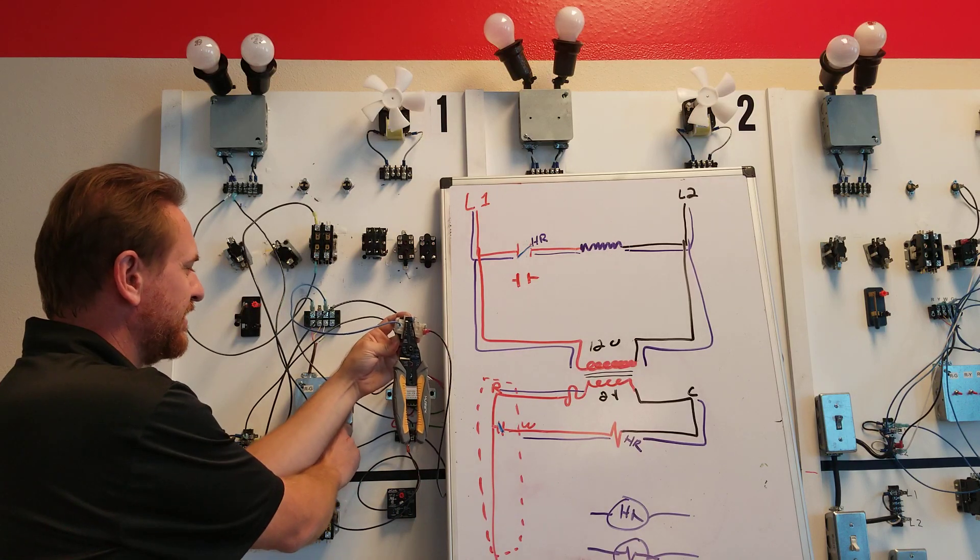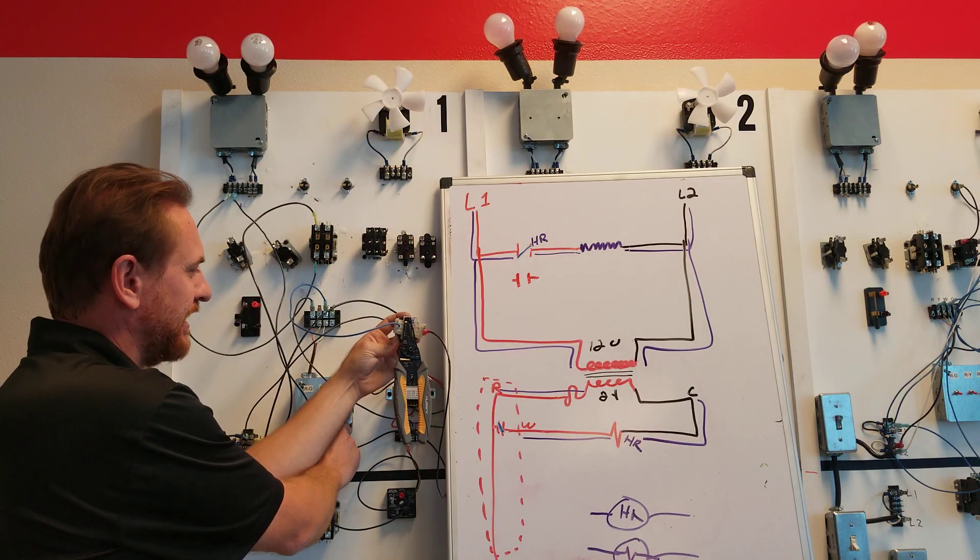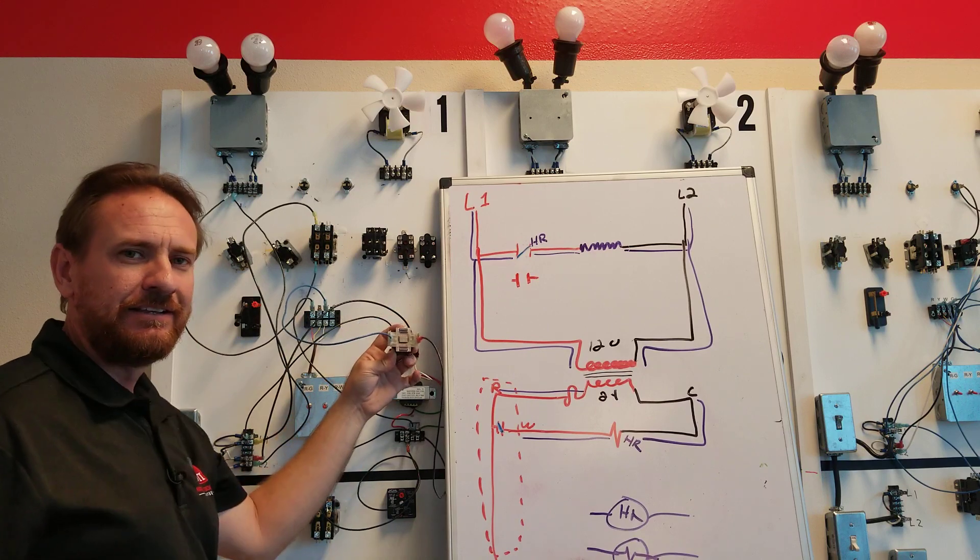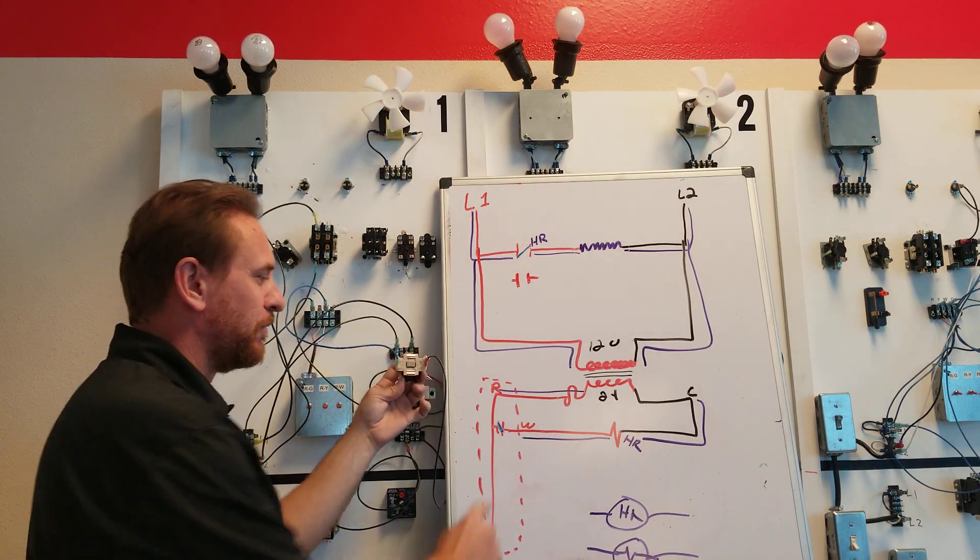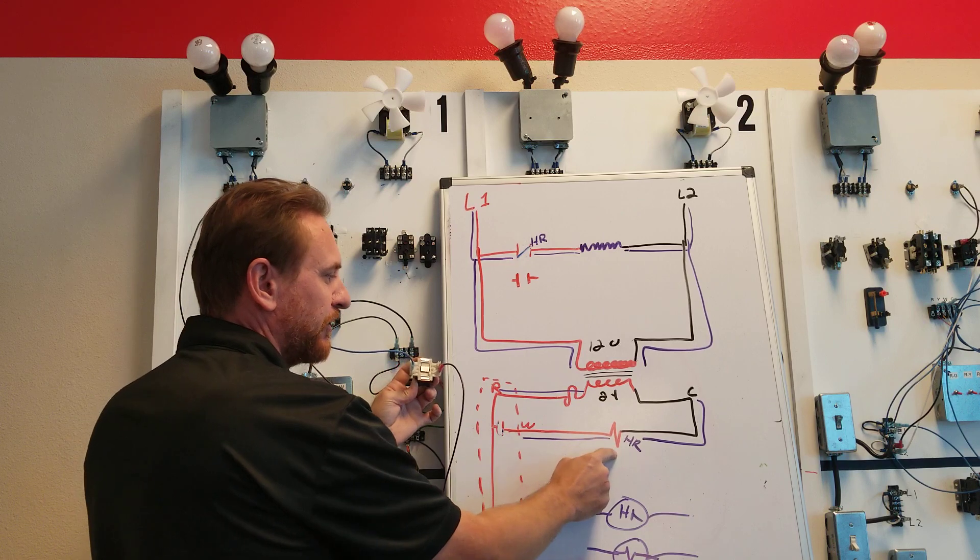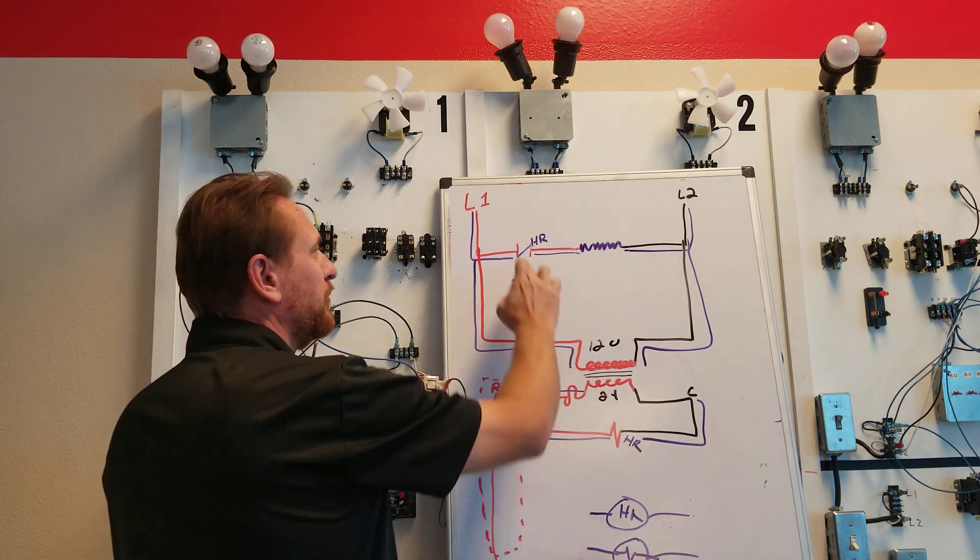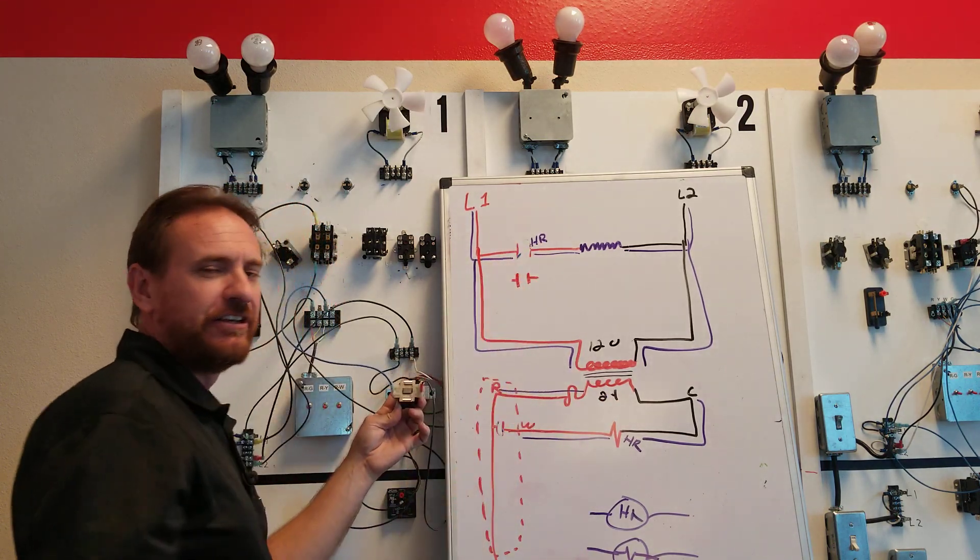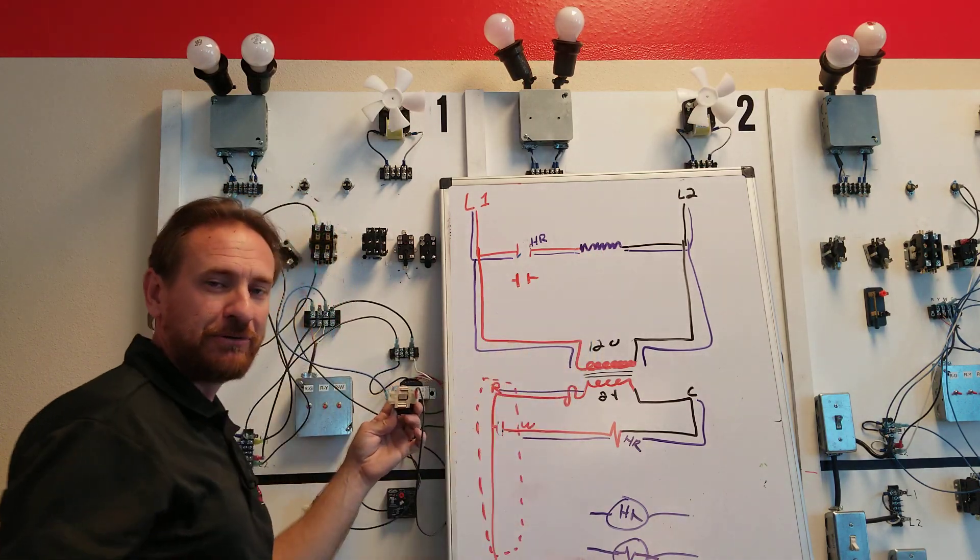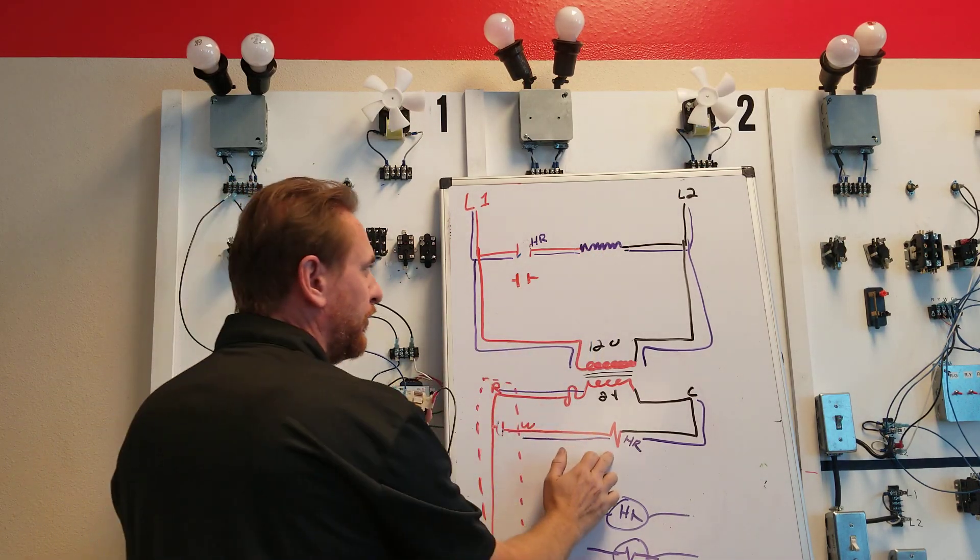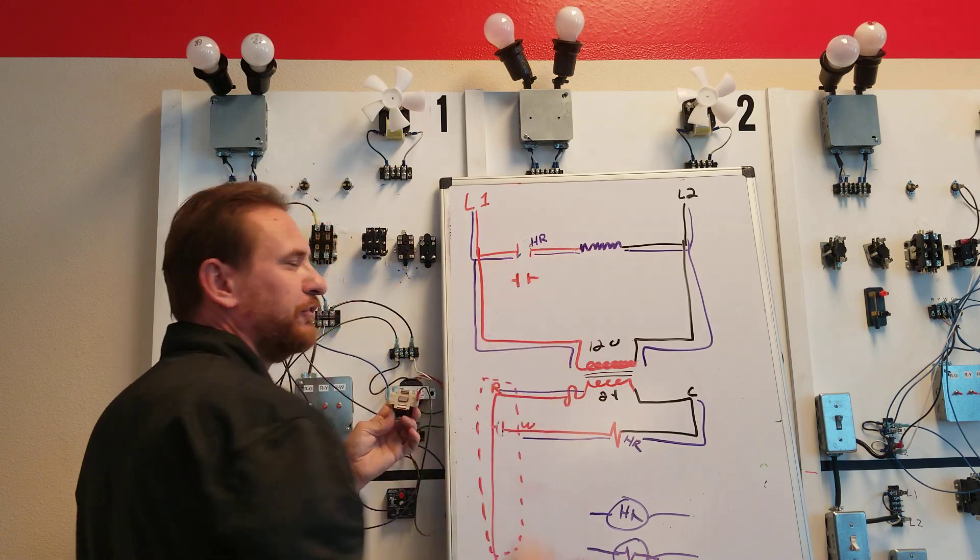When I de-energize the R&W switch of my thermostat it falls down. It's no longer a load. When I open this switch we no longer have a load. Now this load would no longer pull this in and our light bulb or our heater in this case would shut off. So low voltage controls high voltage switches.